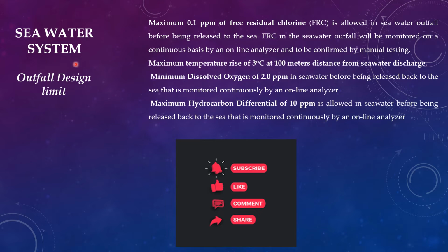Now we can see the seawater system outfall design limits. The seawater system is used as a once-through cooling media. It is to be let out in the outfall after usage in the heat exchanger or cooler, or as the heating media in the LNG regasification plant. A maximum FRC of 0.1 ppm is allowed in the seawater outfall before being released to the sea, and it is discharged back to the sea after being used in the system for cooling or heating.